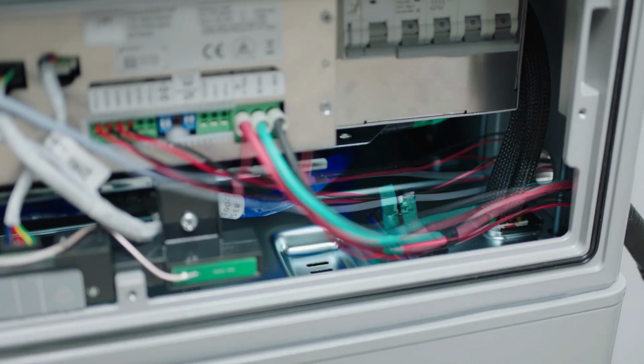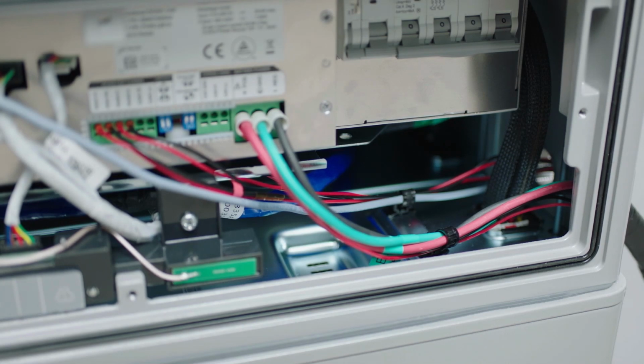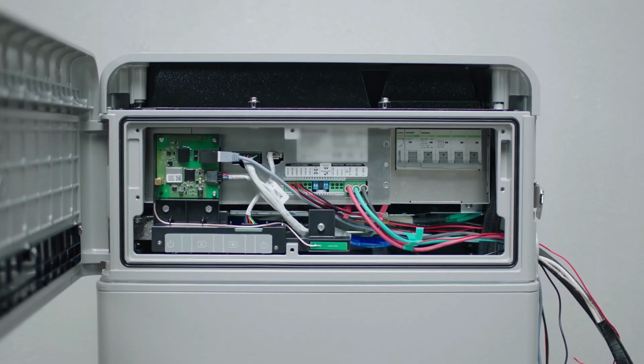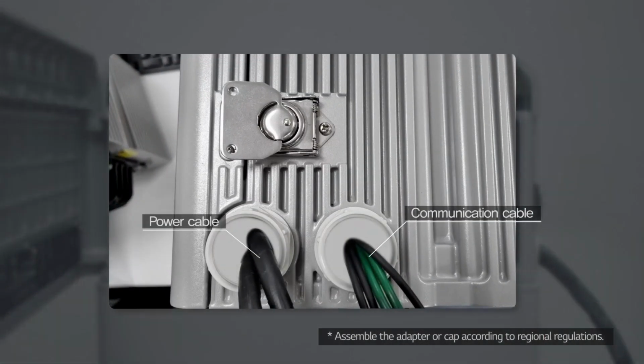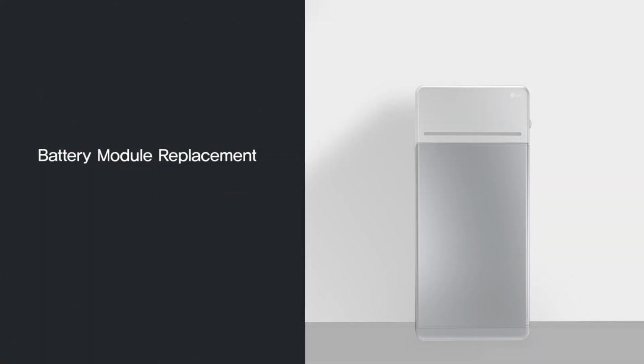Arrange the power cables and communication cables separately using cable ties. Then, apply silicone sealant or putty around the cables at each hole to prevent foreign materials from entering the battery pack. 4. Battery module replacement.